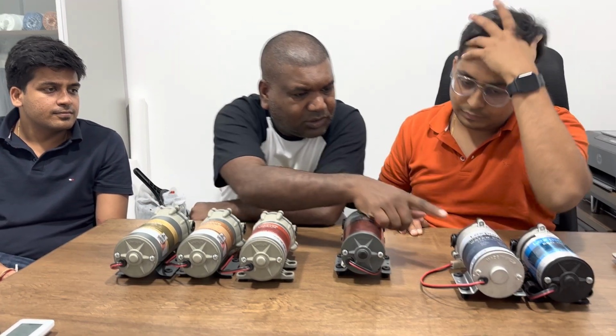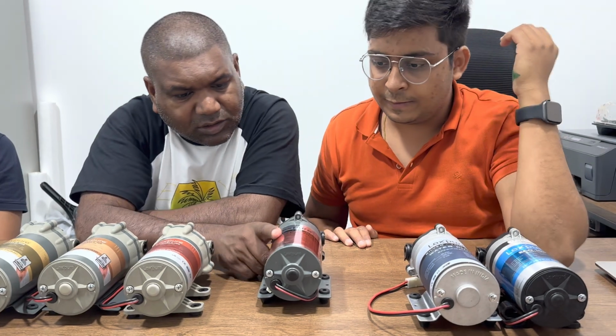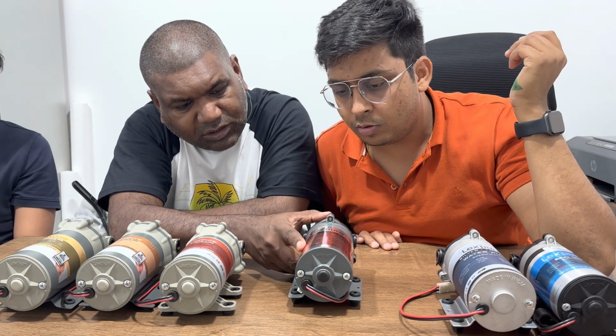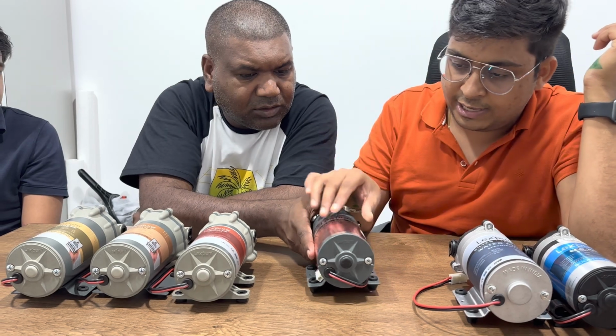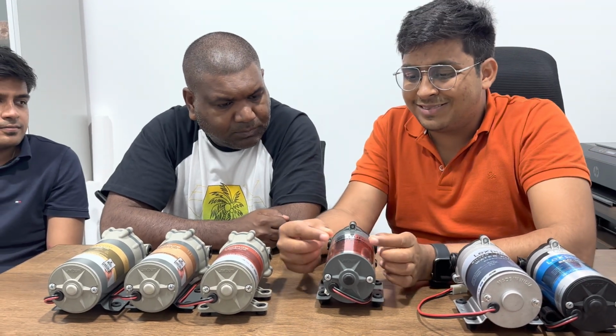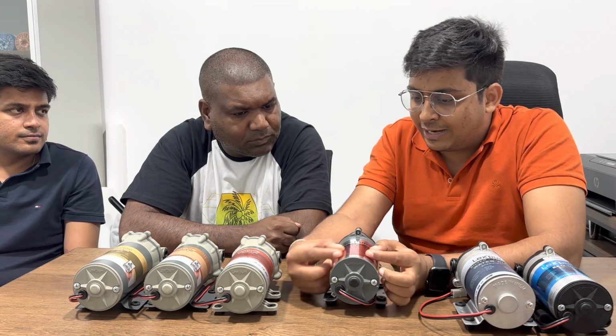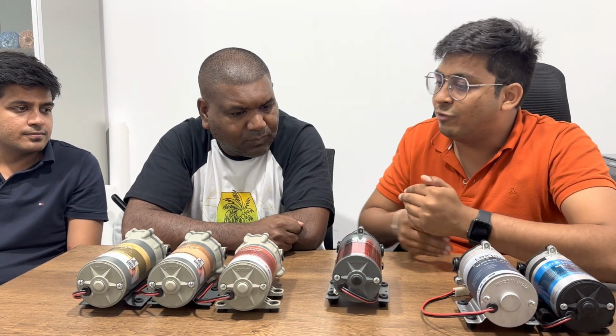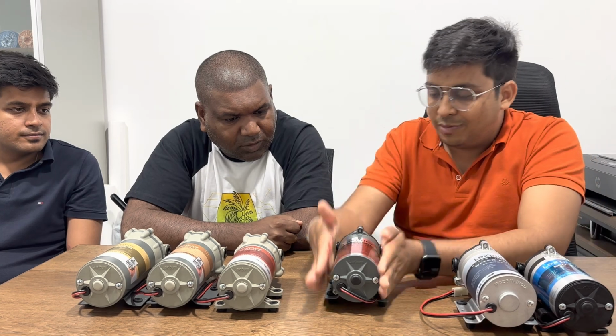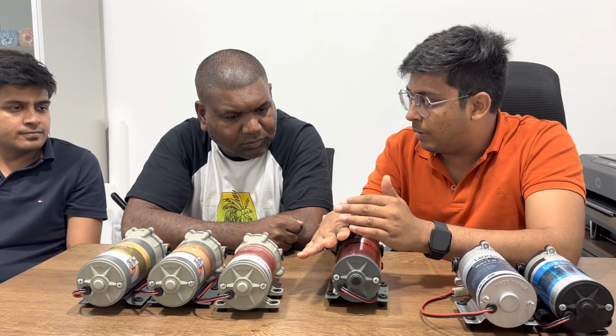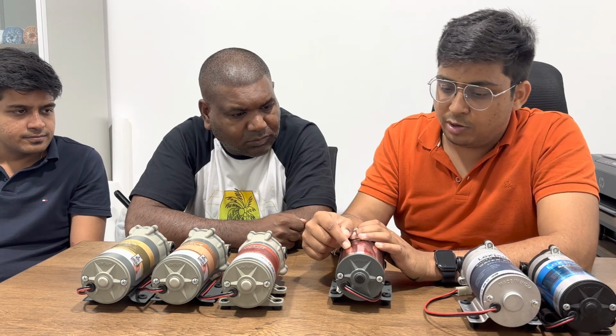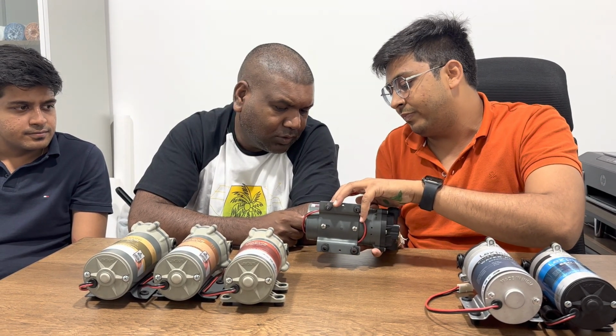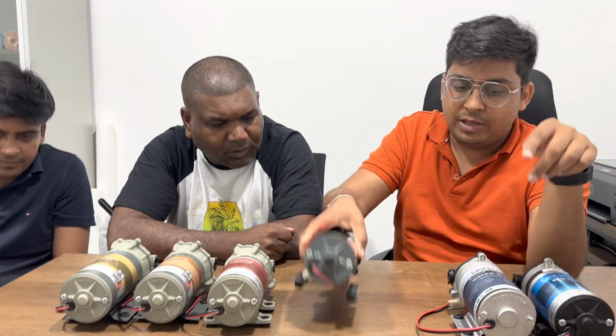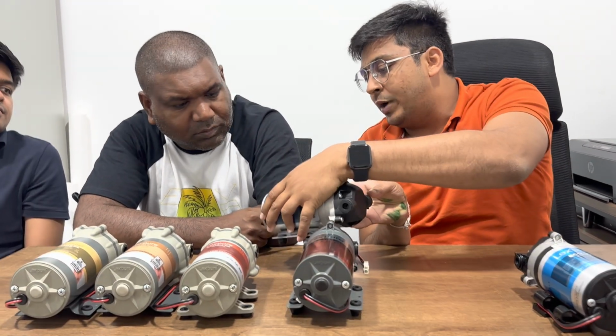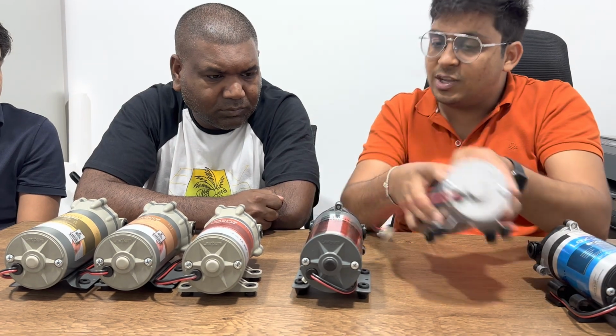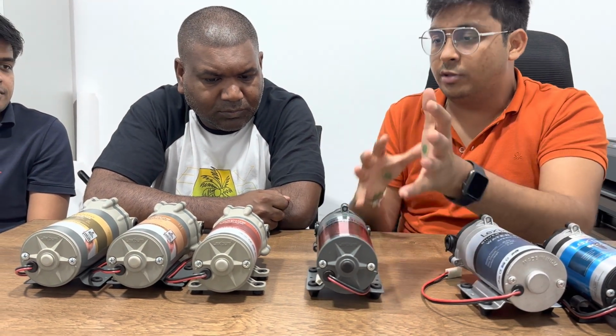So the pressure on that one is 90 psi. Working pressure. This one is working pressure, also 90 psi. I'll explain. These are the current specifications which we have to write for everybody. But at 100 psi nothing happens. At 120 psi nothing happens. The bypass of this pump is 150 psi. So this is the maximum pressure of the pump. The bypass of this pump is 120 psi. Max pressure is 120. That's how you calculate the pressure of the pump.